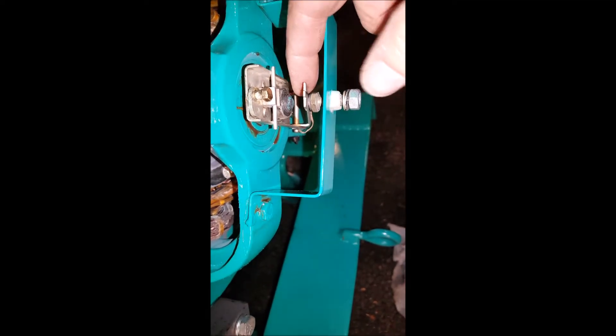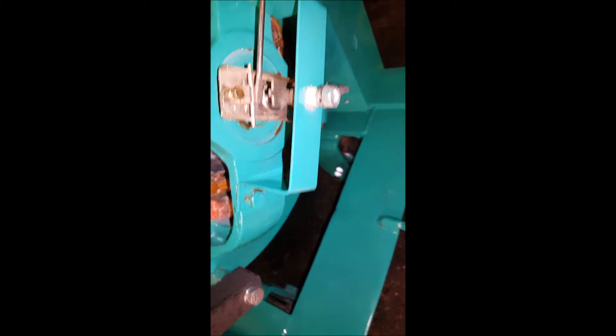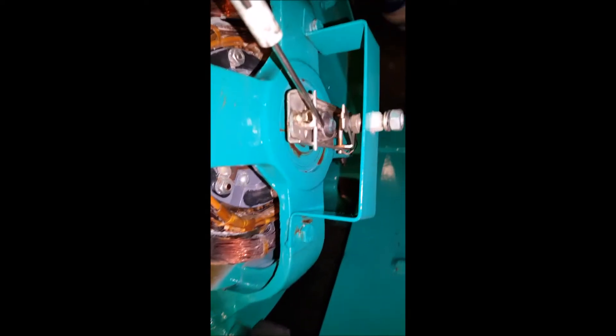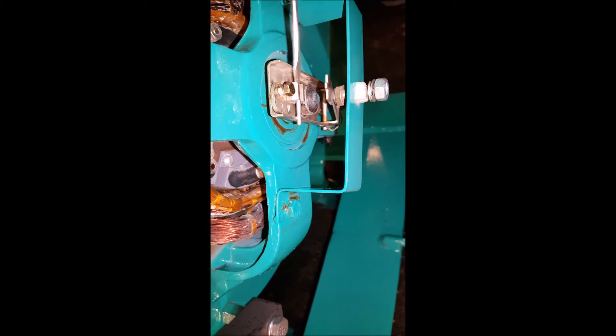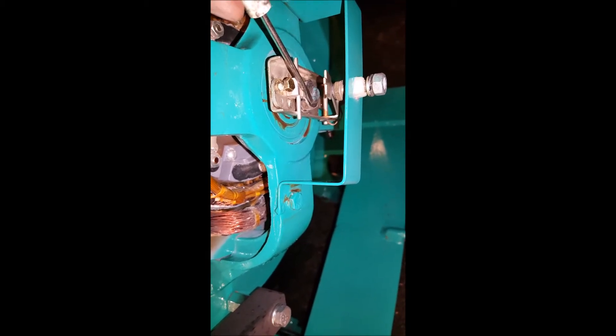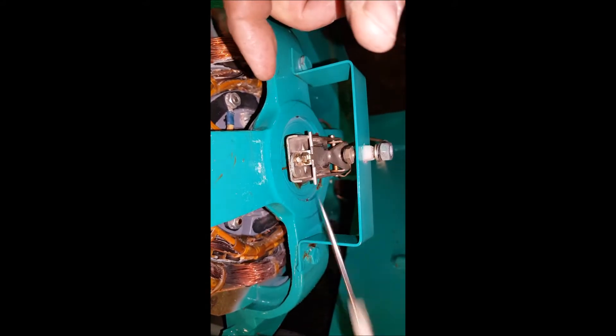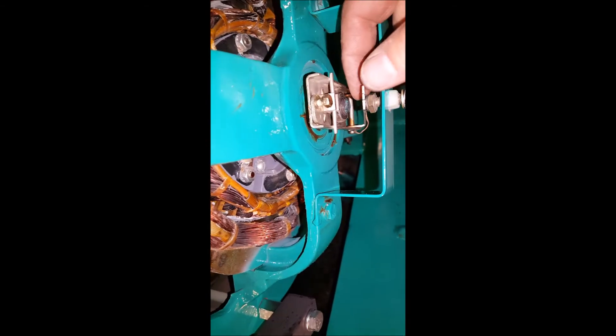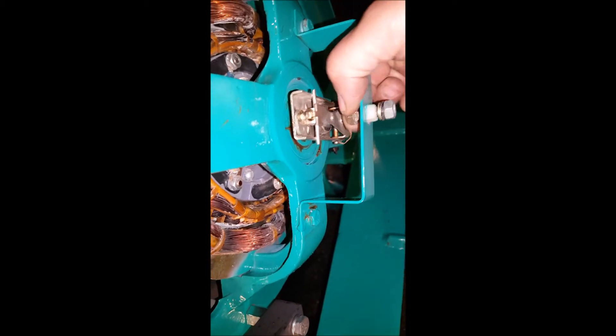There's really no magnet in this little lever. The magnet is this little thing right here — let me get my screwdriver. This is the magnet. It may get a little magnetized, but your magnet is this thing here. So anyway, it can be adjusted two ways: one will remain open when the generator comes to a stop, or another way it will go back and reset itself and rebound back.